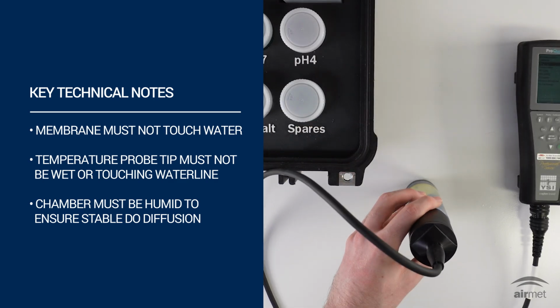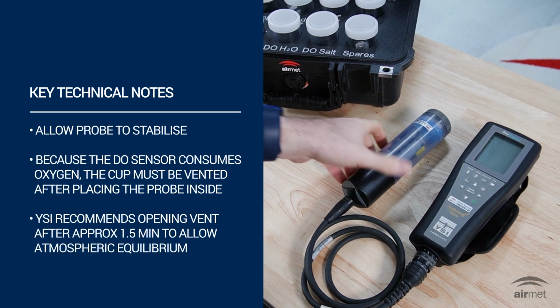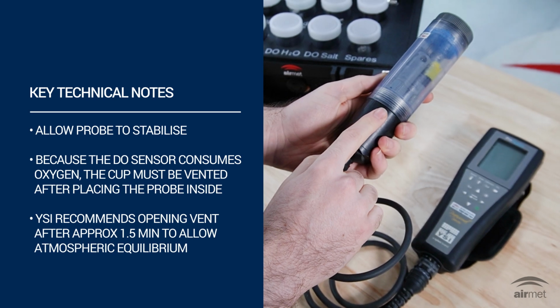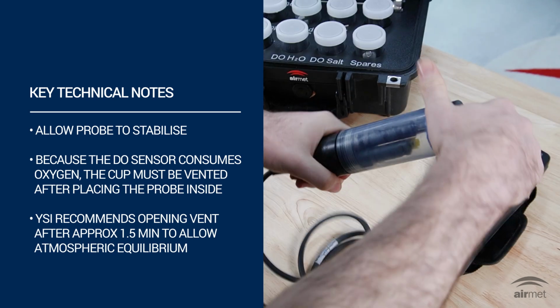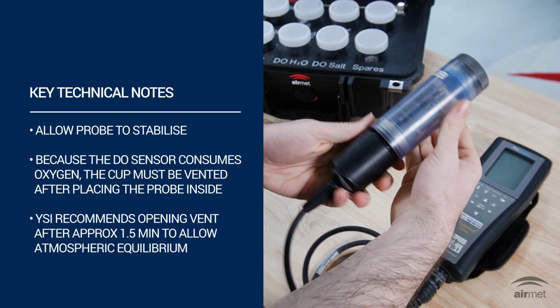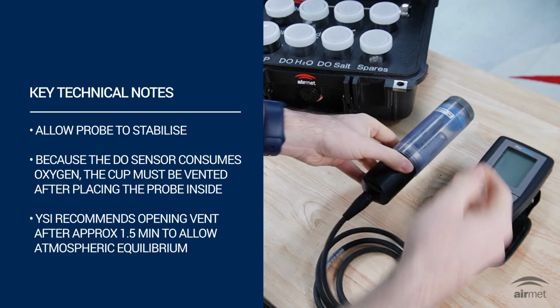Allow the probe to stabilize. Because the DO sensor consumes oxygen, the cup must be vented after placing the probe inside. YSI recommends opening the vent after approximately 1.5 minutes to allow atmospheric equilibrium.